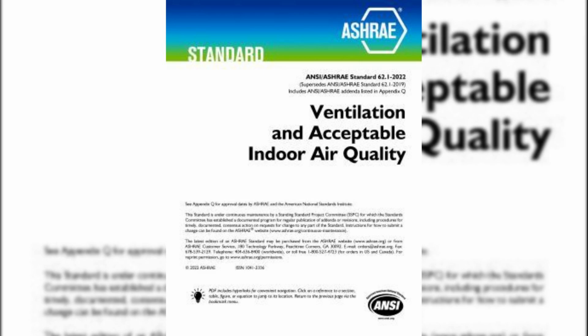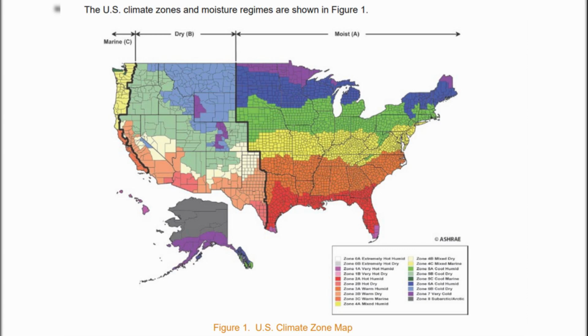Kitchen: 100 CFM intermittent or 5 ACH continuous. Bath: 50 CFM intermittent or 20 CFM continuous. IRC, IECC: most jurisdictions require a dwelling unit mechanical ventilation system meeting 62.2. Many require airflow verification at the register and fan efficacy compliance. 2021 IECC requires testing of whole house ventilation and fan efficacy compliance. Some provisions require HRV or ERV in very cold zones. Balanced packaged HRV and ERV systems are expected to comply with HVI 920 and be tested so you can commission to the required CFM.